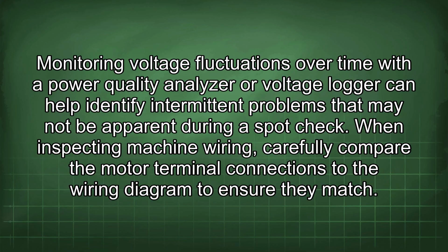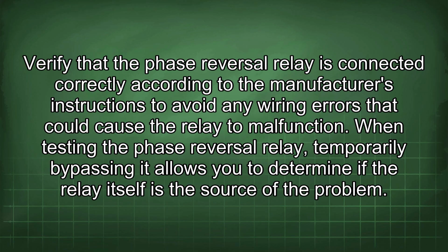When inspecting machine wiring, carefully compare the motor terminal connections to the wiring diagram to ensure they match. Verify that the phase reversal relay is connected correctly according to the manufacturer's instructions to avoid any wiring errors that could cause the relay to malfunction.